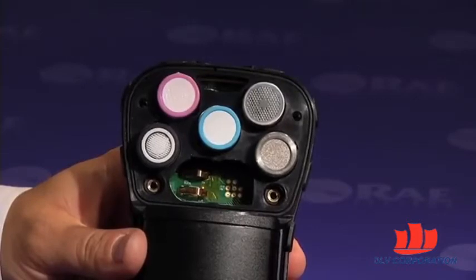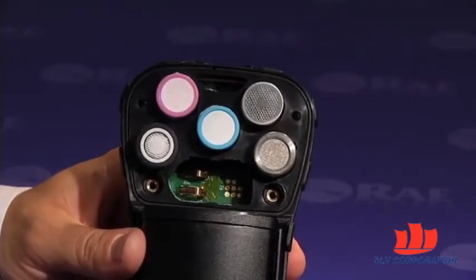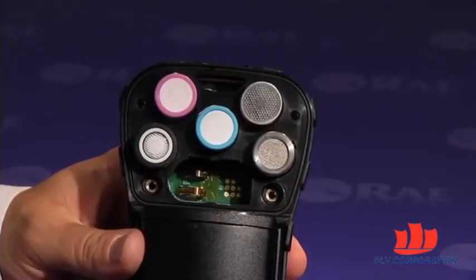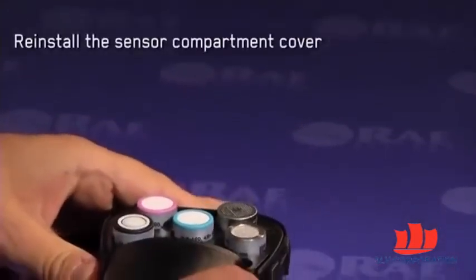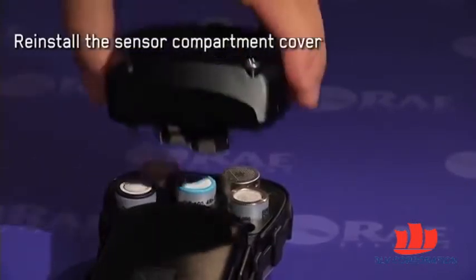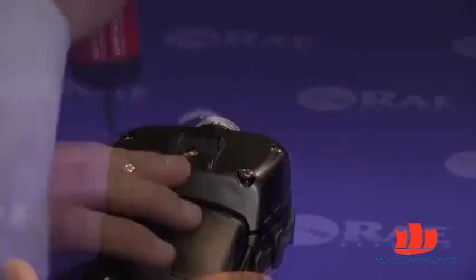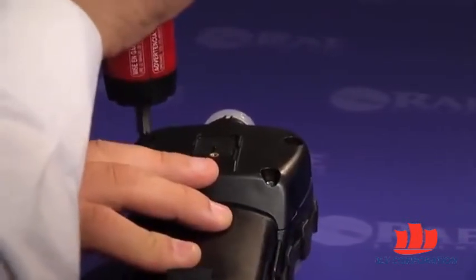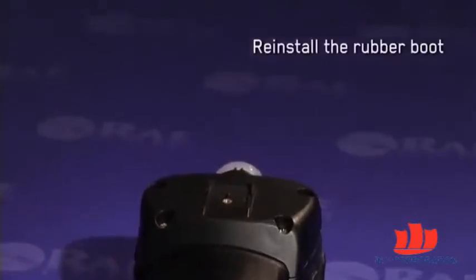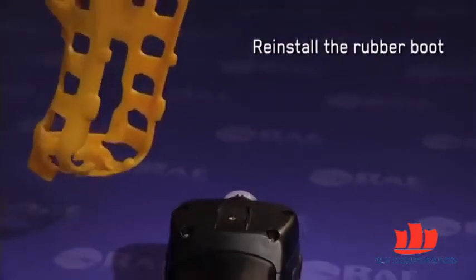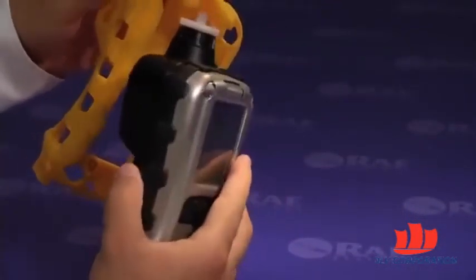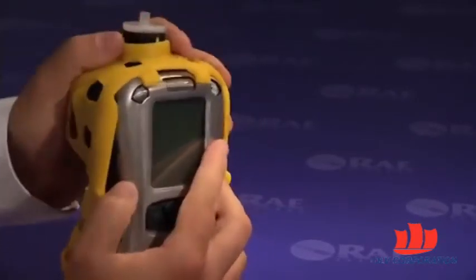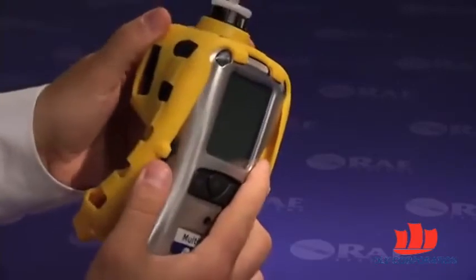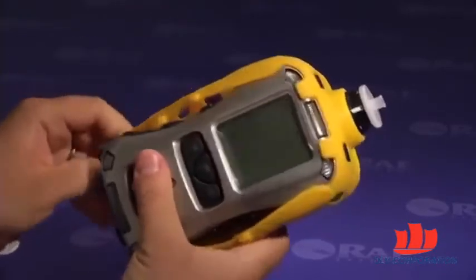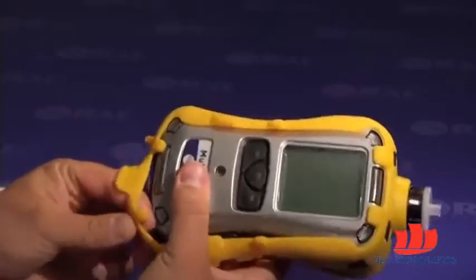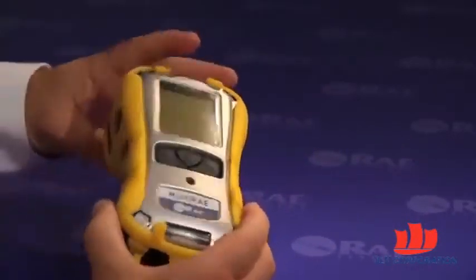Now all you need to do is to reassemble the instrument, reinstall the rubber boot and the belt clip, and the sensor replacement process is complete. First, let's reinstall the sensor compartment cover. We'll reinstall the 4 Phillips screws that hold it in place. Next step is to reinstall the rubber boot. The rubber boot reinstallation process is actually the reverse of the rubber boot removal process. So we would start reinstalling the rubber boot from the very top by inserting the filter and the gas inlet into the respective top parts of the rubber boot, and then reinstall the bottom part of the rubber boot.